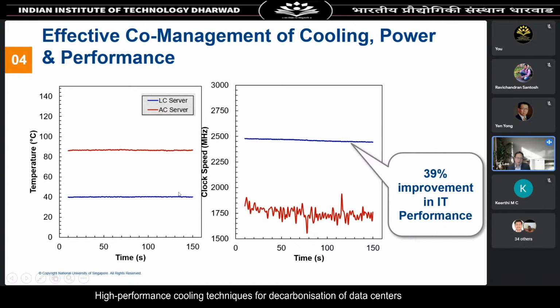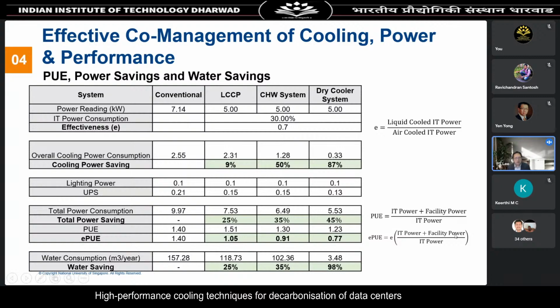The corresponding temperature is exactly what we discussed earlier: the reduction here is as much as 45 to close to 50 degrees Celsius. Again, once you effectively manage your chip temperature, you get wonderful side benefits in IT performance improvement and IT power consumption reduction. This slide shows the comparison in terms of PUE.